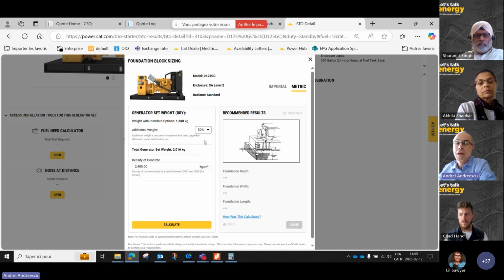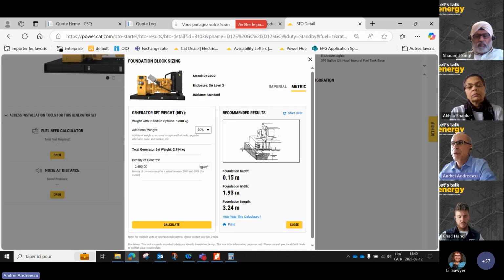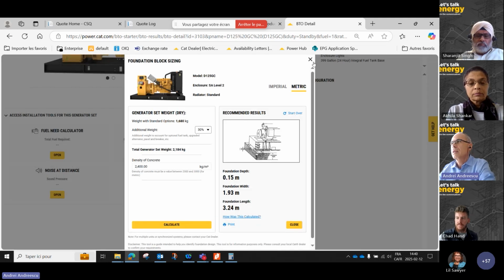Let's say we add 30% for fuel or other options we may install locally on the generator set. Based on the density of the concrete, the tool calculates the depth, width, and length of the foundation. The length and width are based on the weight and length of the generator set, and the depth is based on a formula given here, everything coming from the Caterpillar application and installation guide.